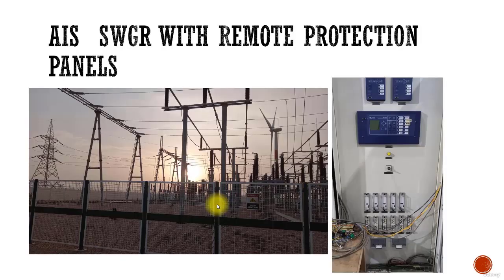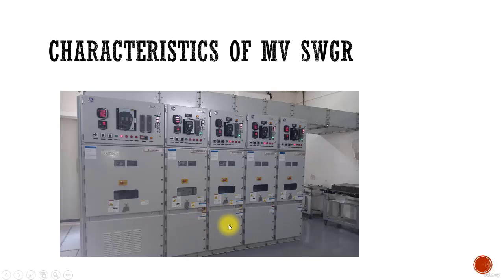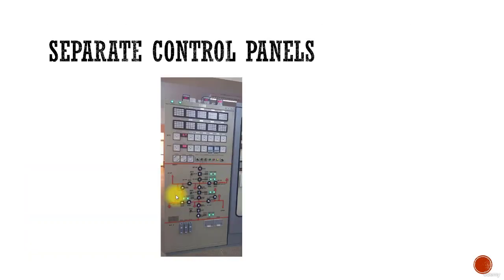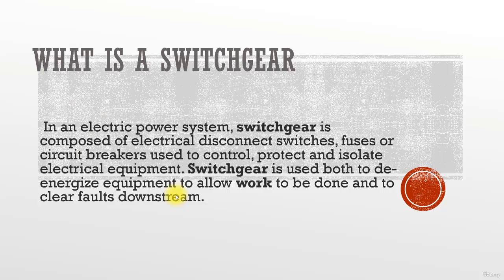But this also comes with a hazard. The hazard is because if the operator is doing operation in front of the switchgear, then there could be the hazard of flash. That's why it's always recommended to make a remote control panel as well with the MV switchgear. So this is a disadvantage of the MV switchgear. So this is all about an intro. Later we will learn together about different compartments of the switchgear, different types of breakers, and different characteristics of the MV switchgear. Thank you very much.